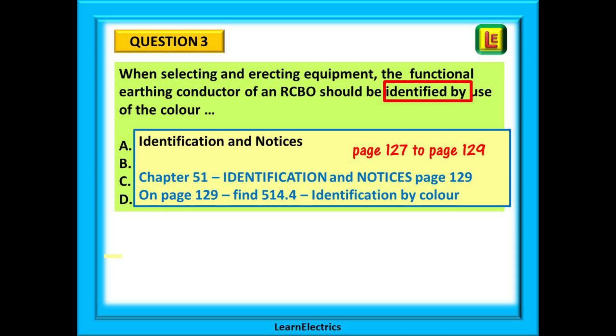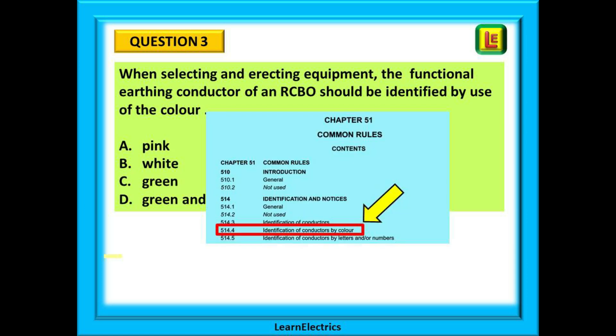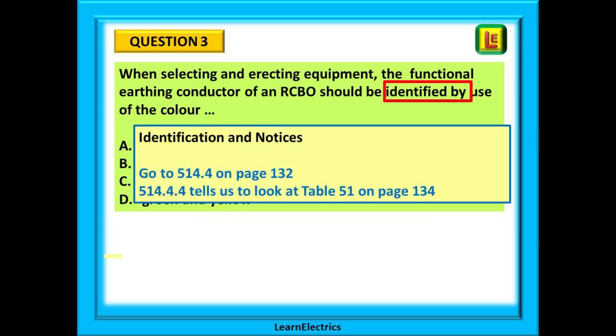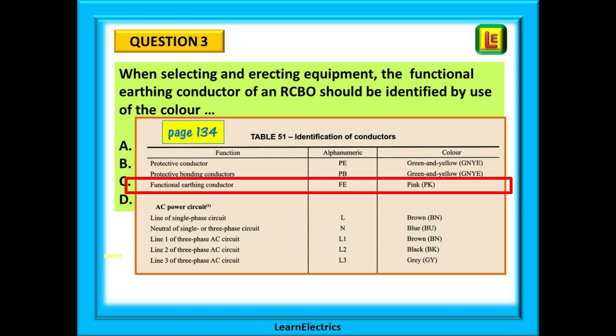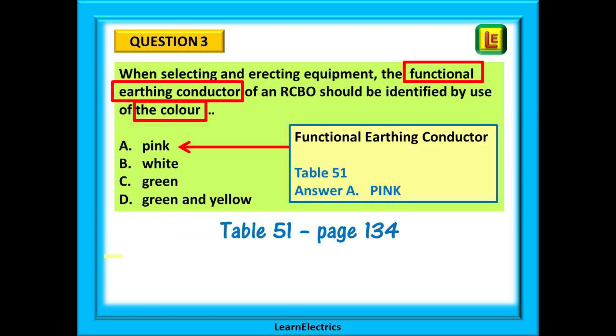On page 129 is another contents page just for chapter 51, with more detail. About halfway down we find regulation 514.4, identification of conductors by colour. Going to regulation 514.4 on page 132, we scan down to find 514.4.4, which tells us to look at table 51 on page 134. On page 134, table 51, identification of conductors — look for 'functional earthing conductor' near the top, and there is the colour pink. This used to be white, but now it's pink, and highly likely to come up as an exam question. So our answer is A, the colour pink.